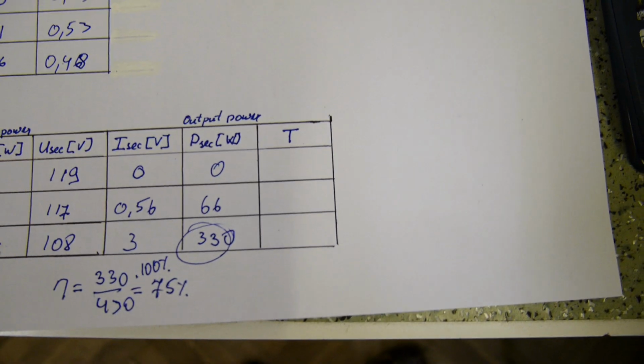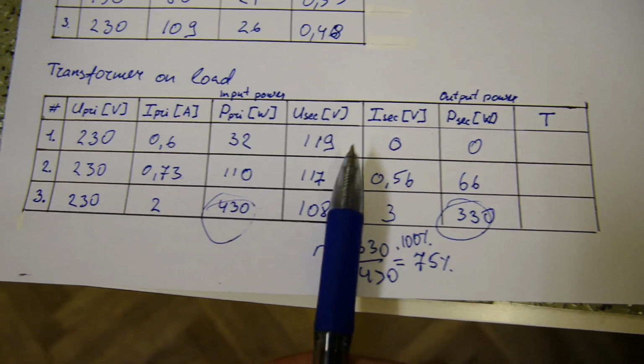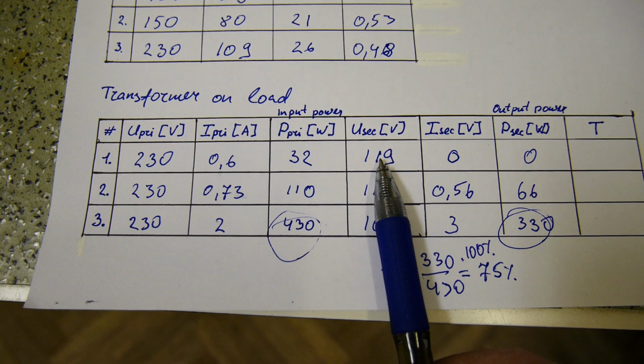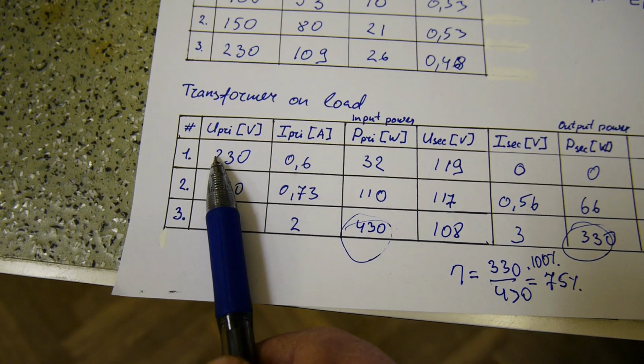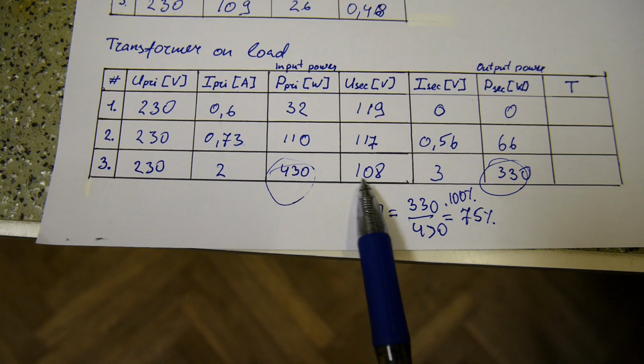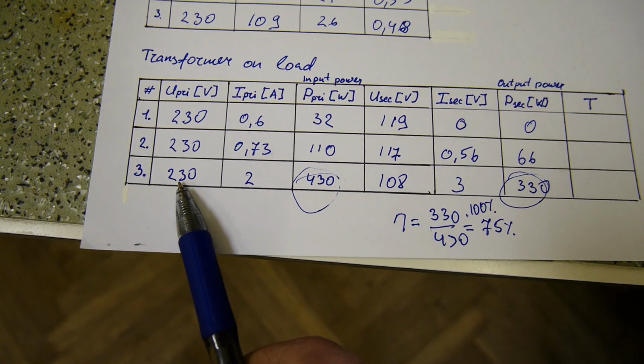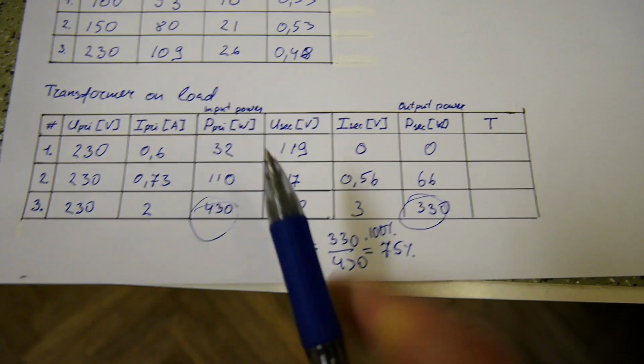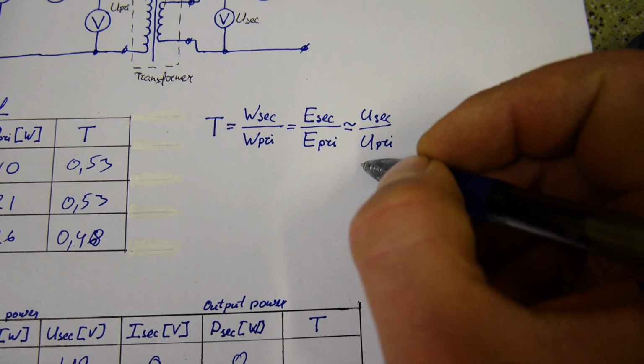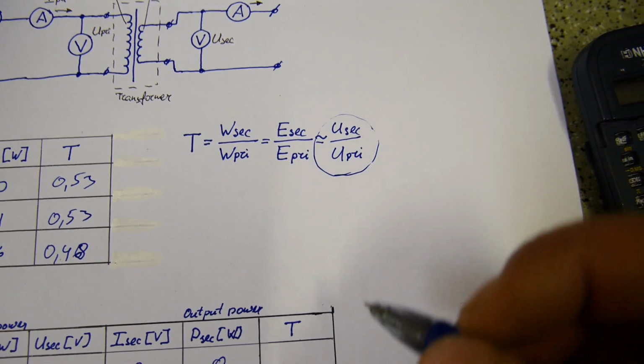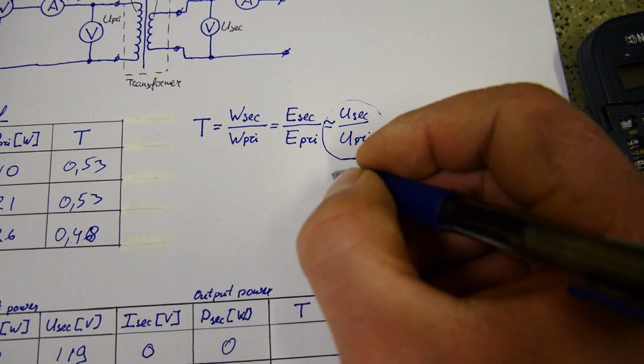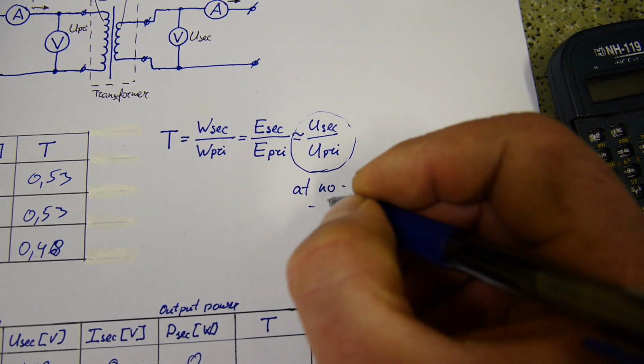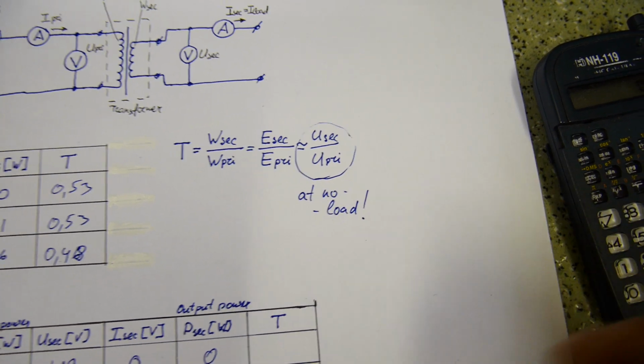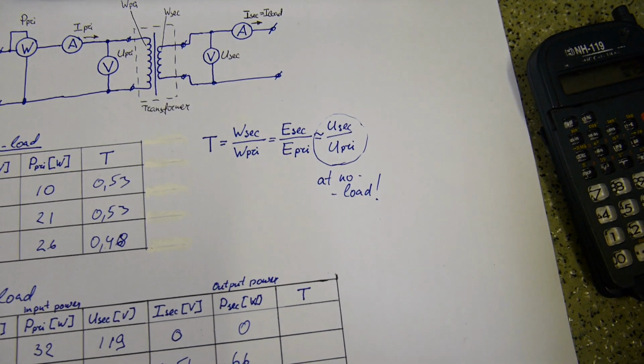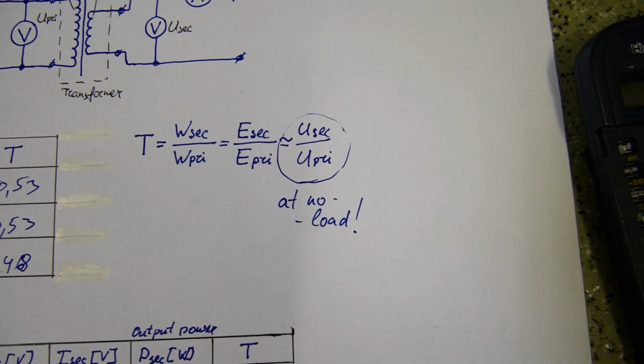Okay, what about turn ratio? Look, if you will use voltages as it was here, you will get wrong results, because 119 divided by 230 is not the same like 108 divided by 230. So this method is not applicable. So you have to remember that this one can be used only if your transformer is operating at no load. Yeah, so load must be disconnected if you would like to calculate your turn ratio.